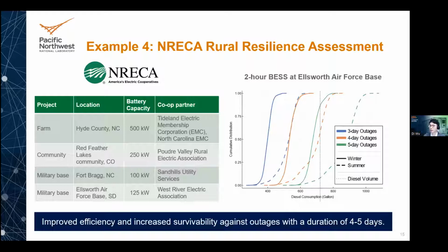Here are the resiliency assessment results for a 2-hour battery energy storage at Ellsworth Air Force military base. This plot shows the cumulative distribution function of fuel consumption for outages with different durations in different seasons, and this vertical line shows the on-site fuel storage capacity. Without the battery, the system cannot survive any outage longer than 2 days.